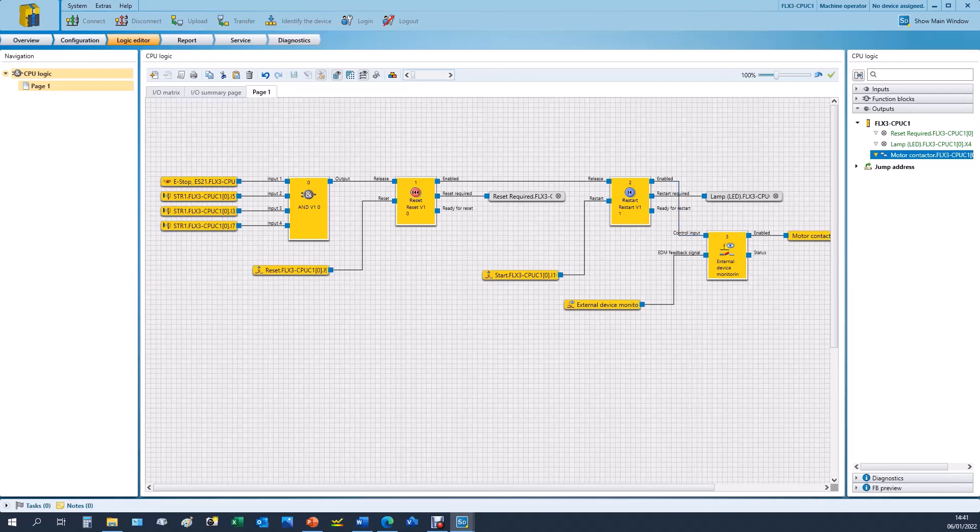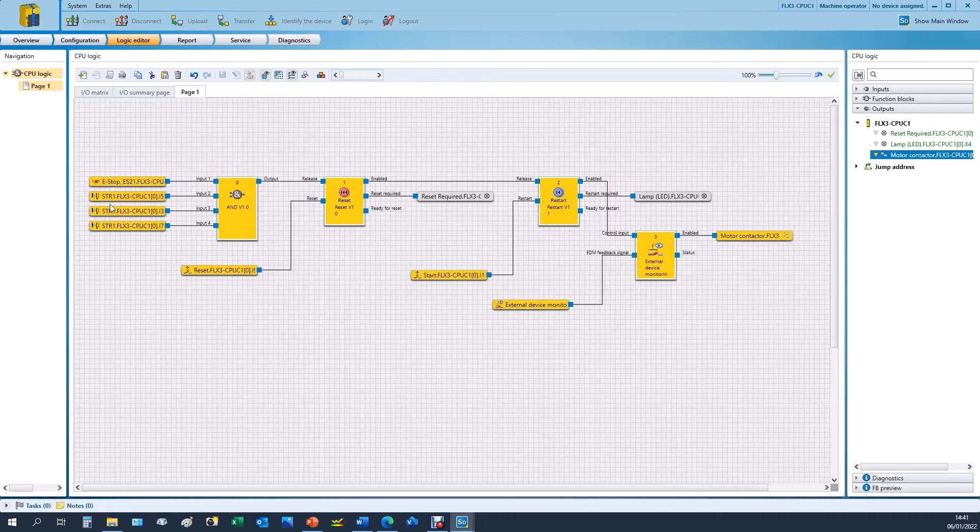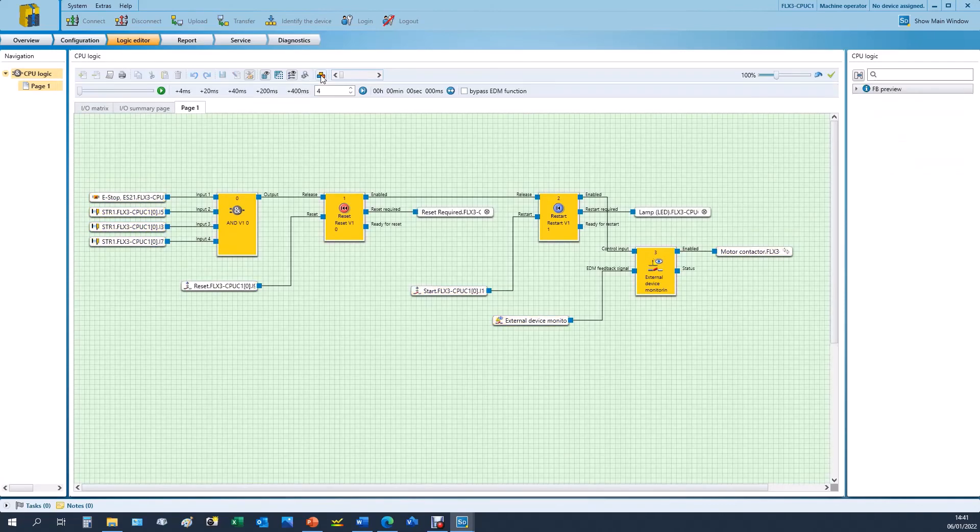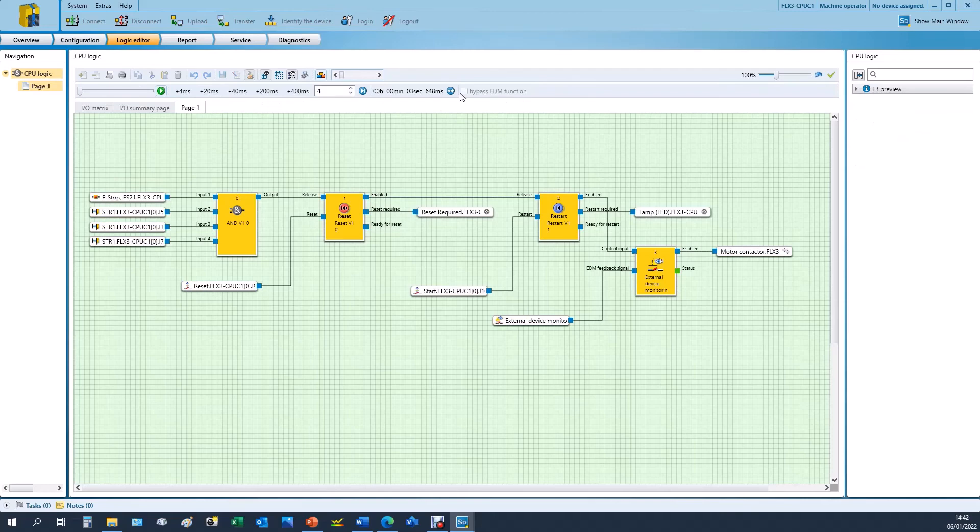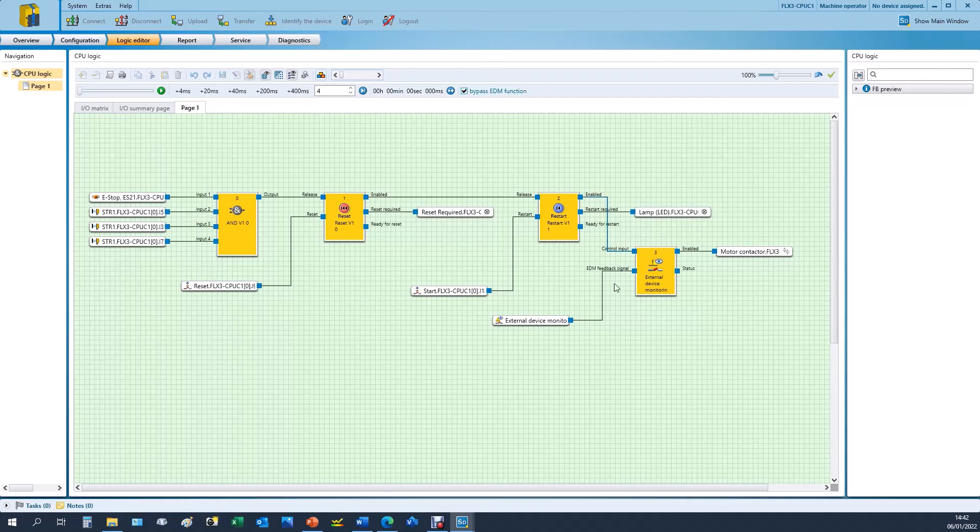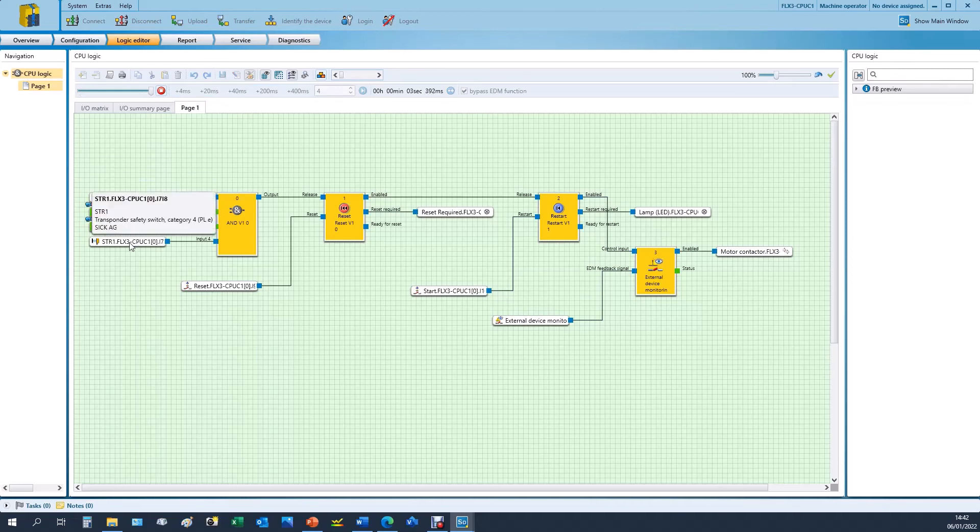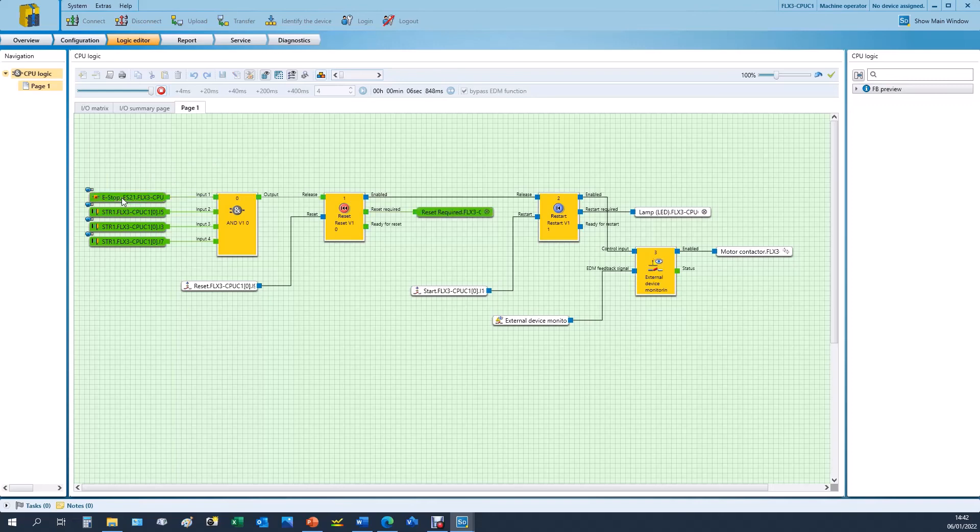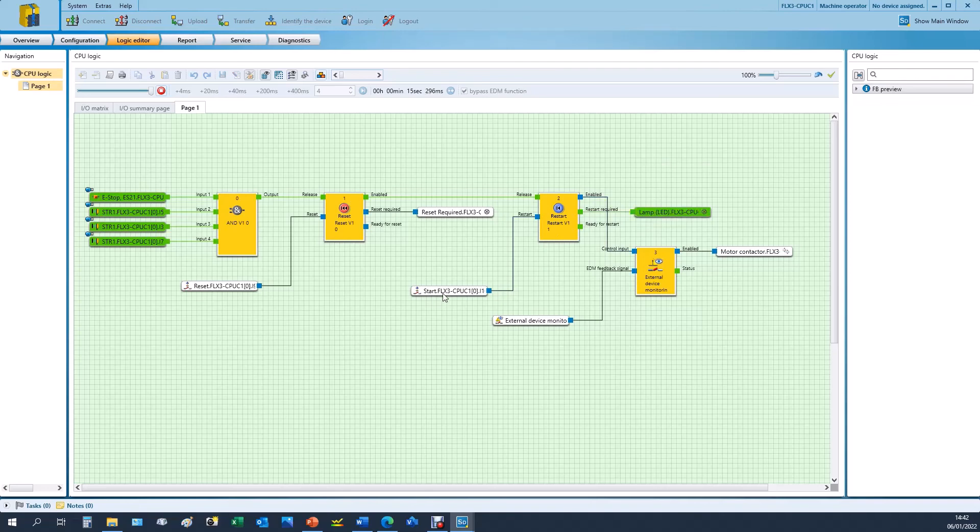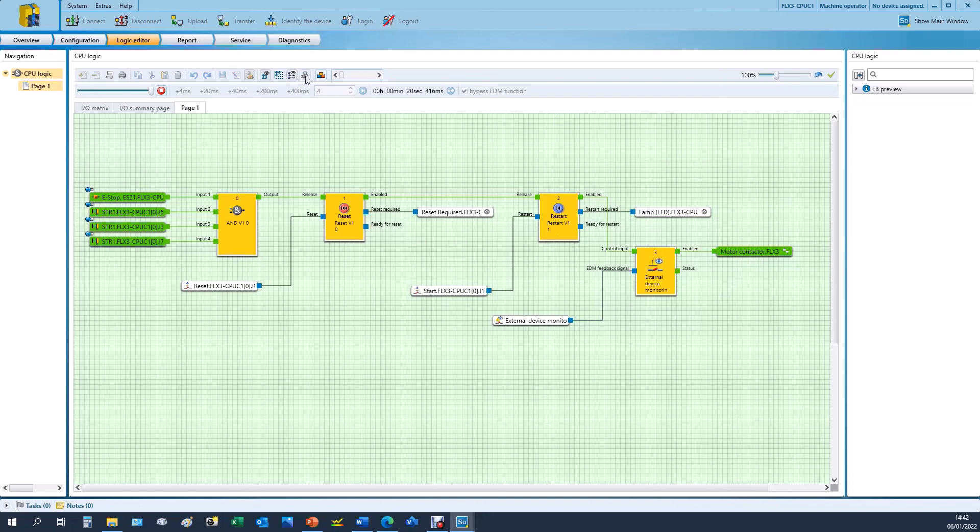If you want to test any logic as part of your verification and validation process in the software, we have this simulation mode at the top. When you click this you can run in real time or step through in certain milliseconds. We can also bypass the EDM function if you think this may cause a problem because you can't click the EDM input at the same time as the enable going high. So you can bypass that EDM function for testing purposes. And then when you're running you can start to turn on and off devices. So all the doors are shut, the e-stop button is healthy, the reset is required on the machine. You press the reset, you let it go, this now enables the restart function block. So a start is required, you start the machine, and the contactors go high.